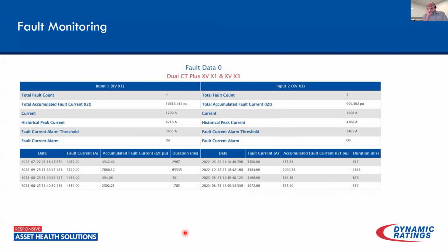We talked about the increased fault activity and things like that. Monitoring the fault levels and the fault activity on your transformers can be a good idea. Putting this right in the transformer monitor is a good idea, because then it's going to follow the history of the transformer. It's not like your relays, which may change over time, and you've got to save that value. In this case, the online monitor is tracking this over the entire life of the transformer. It's monitoring the number of faults, the I squared T, the total accumulated fault current on that transformer, existing values, historical peak fault currents, and then a history of those faults and stuff like that. So, seeing this type of activity, one, it can identify when we've got excessive fault activity, but it's also going to give us an indication as to the mechanical history that that transformer is experiencing.